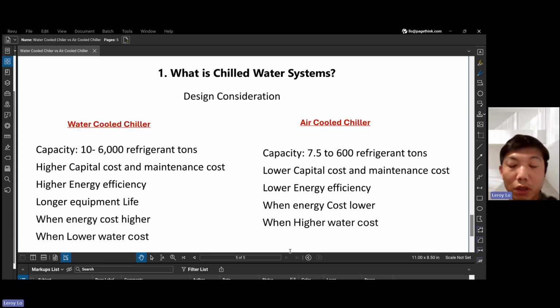So in this slide we're talking about the design considerations. Number one will be cooling capacities. Water-cooled chillers typically range between 10 to 6,000 refrigerant tons. So it's quite a lot, depending on your applications. And air-cooled chillers are typically in the range between 7.5 to 600 refrigerant tons. So this is relatively smaller. You can see it's about 10 times smaller than the water-cooled chillers in terms of capacities.